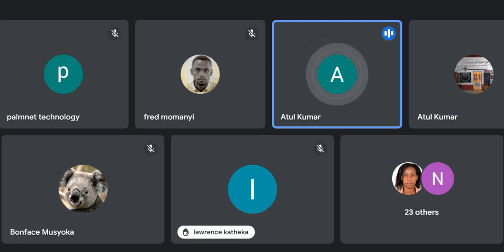And your question about the CyberKnife, for example, why do we have a single 6 MV energy? CyberKnife is a very compact LINAC. Apart from the bigger design of the CyberKnife, the majority of the design is the robot, and only the head of the CyberKnife that you see is the LINAC. So the size of the LINAC compared to the entire CyberKnife is very small. It's a kind of LINAC grabbed by a robot. A robot is grabbing that LINAC, so that LINAC has to be very compact.